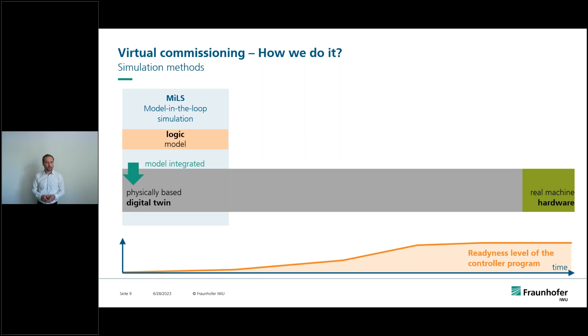In the later phase, when our control system is defined and we know the manufacturer of it, many manufacturers provide a simulation of their controls, and we can connect this simulated machine control to our digital twin via communication protocols such as TCP/IP or OPC UA to give the demand values to the simulation model.